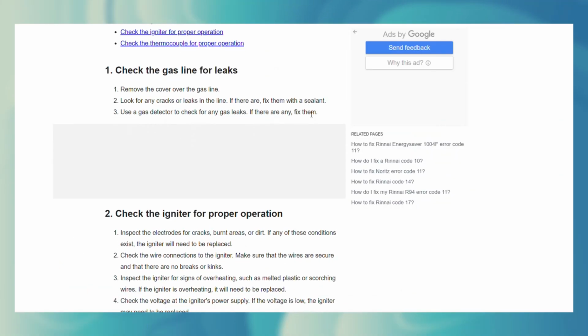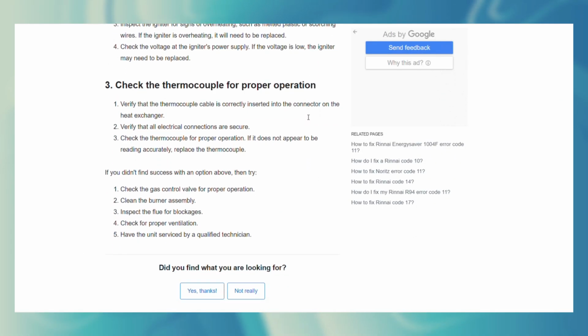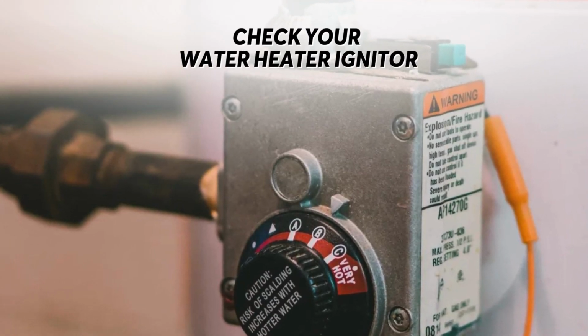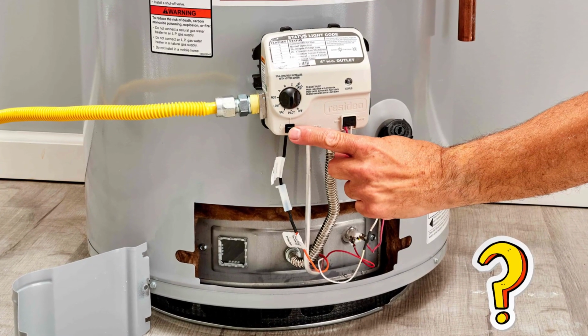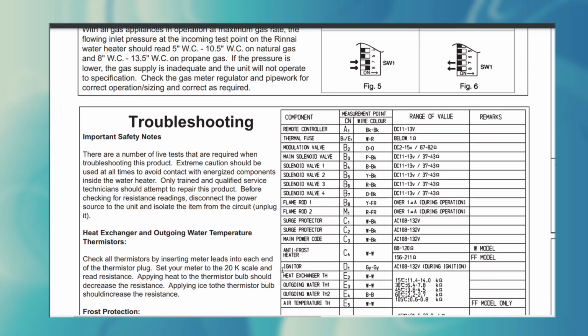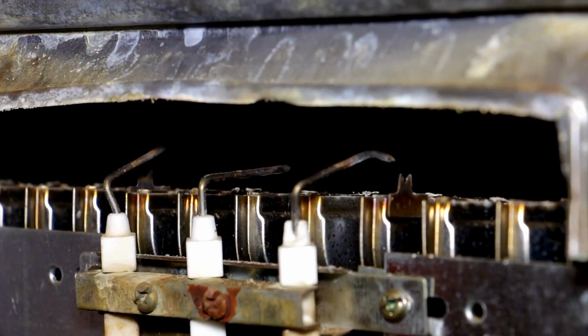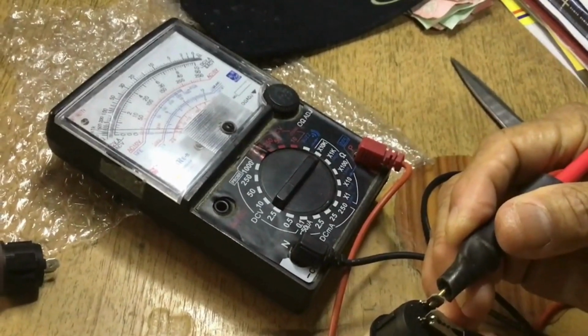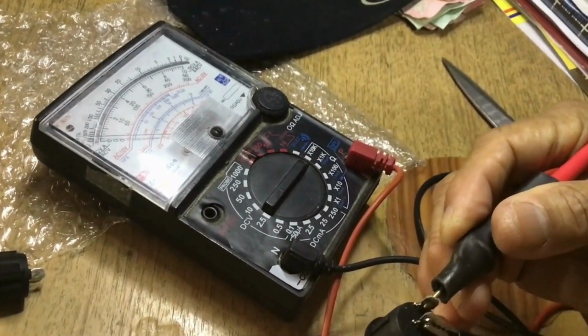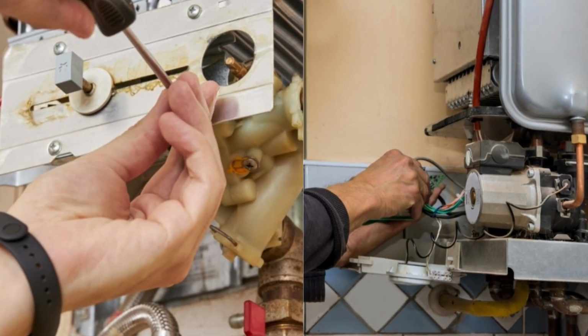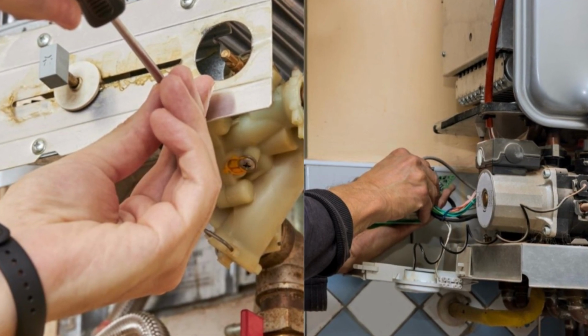Now let's look at the best solutions you can apply to fix the error code 11. Check the water heater igniter. To determine if your igniter is the problem, do the following. Inspect the igniter for dirt, scale, and carbon residue. Clean it according to the instruction manual. If the igniter does not spark, use a multimeter to check if the voltage your heater is receiving is enough. Check for loose or damaged parts and replace them as necessary.